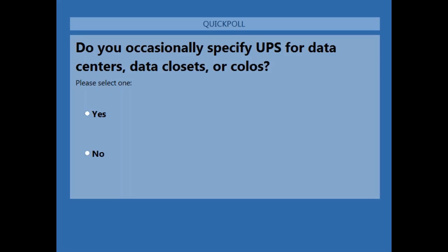I have a question. How does the UPS share load in a distributed redundant system? They don't. There's no active load sharing. If you parallel two UPSs, they will actively share the load. In a distributed redundant configuration, it's up to how you connect the load between all the units. It's a question of balancing the load between the UPSs. They don't really know how the load is shared, and that's a concern.